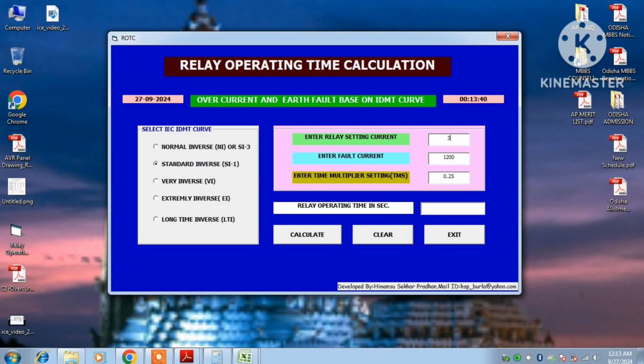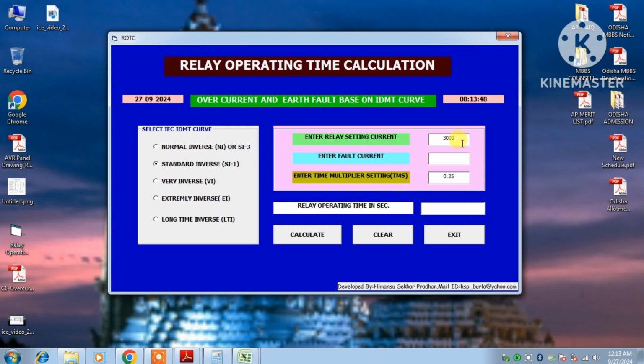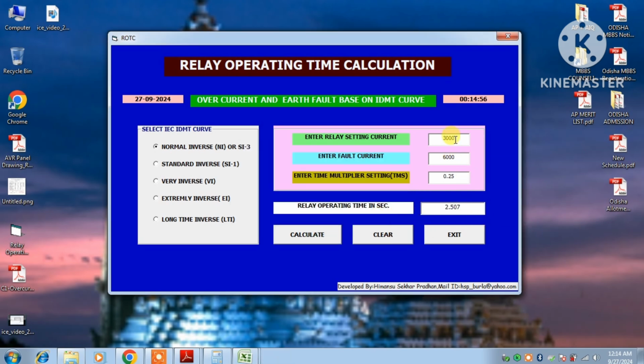So you have to enter 3000 or something. Calculate. In this case, the fault current should be higher than the setting current, so it will not accept a lesser value. I have to enter 4000 amps. If you calculate here with normal inverse, it will operate in 6 seconds. So first, the entry cell will not accept an alphanumeric value. Second, the fault current should be higher than the setting current. If the fault current is the same as the setting current, it will not accept it. So I will take 6000, and it will accept. The fault current should be higher than the setting current. Like that, you can calculate it.